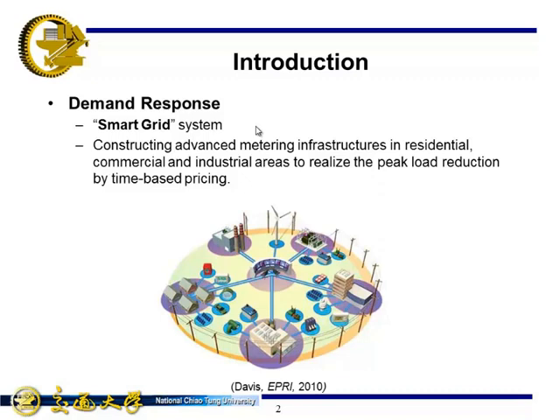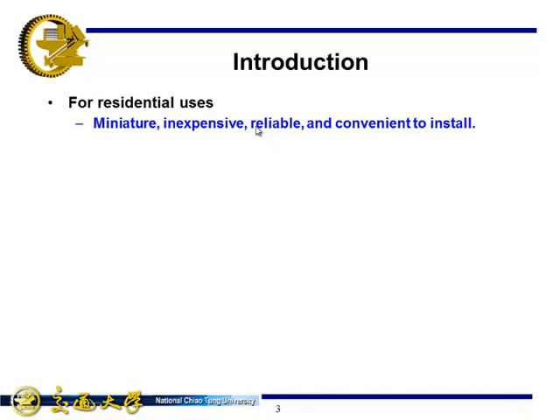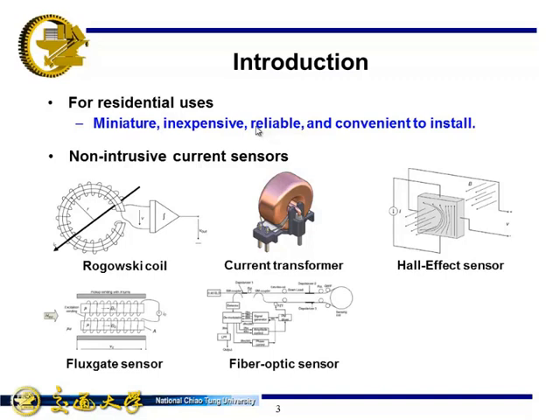Power sensors are required in the electrical management system. For residential uses, miniature, inexpensive, reliable, and convenient to install and use are the key features. The contactless sensing scheme would be the prevailing scheme. The contactless current sensors are mostly based on magnetic sensors like Rogowski, current transformer, Hall-effect sensors, flux gate, fiber optic, or piezoelectric.